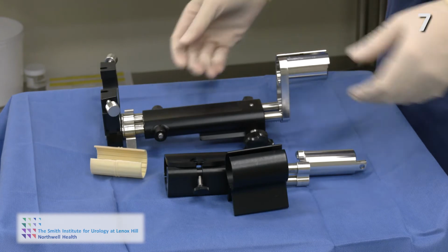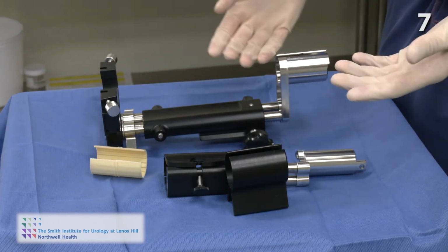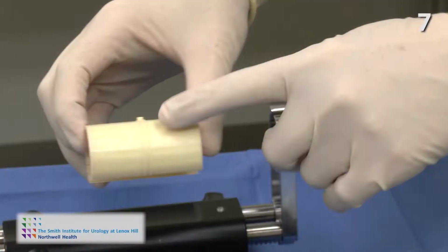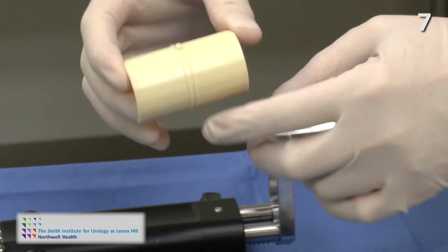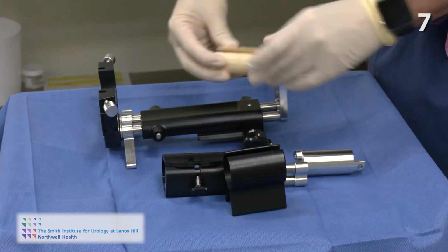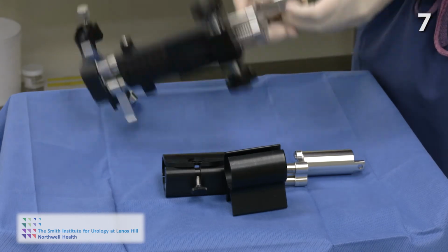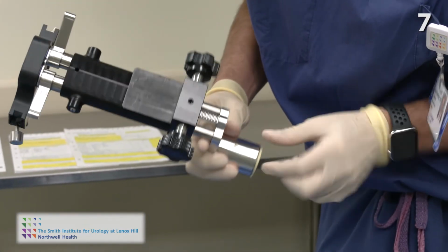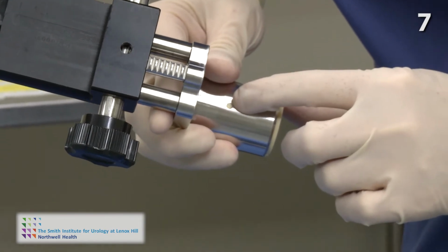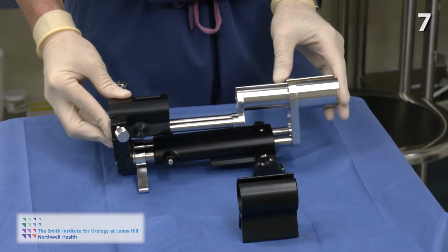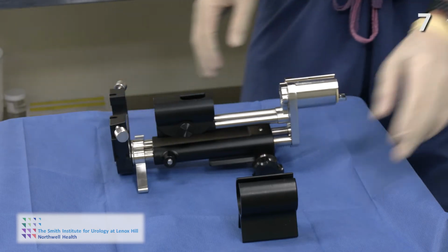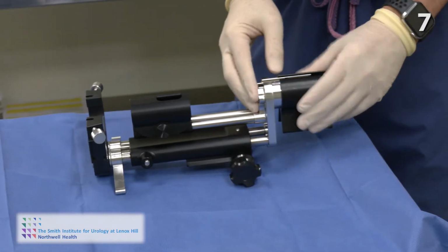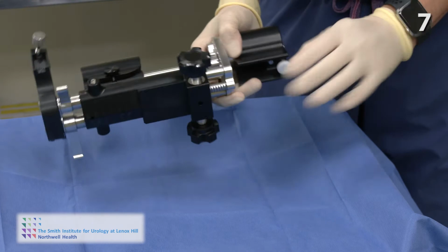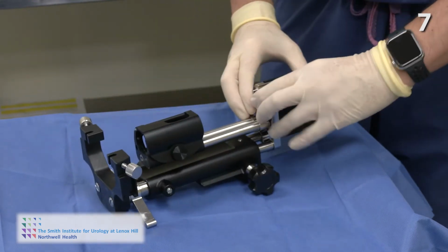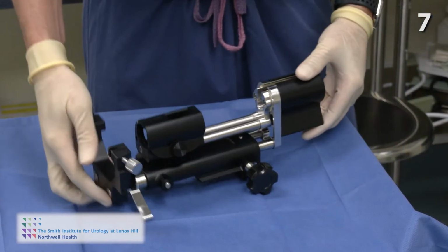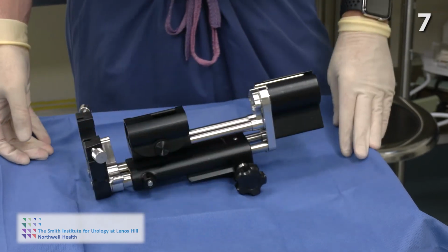And these are the pieces that you have to understand that can fall apart and have to be put back together. This has a center point here that locks in place, as well as a slide or a track. All we do is slide that back in. There's a little hole where you can see it lines up and pops in the hole right here flush. We slide the ultrasound arm back into position. The black piece slides over the back. The white knob we pull down, it slides forward, and we lock it in place. Now the stepper has been put back together.